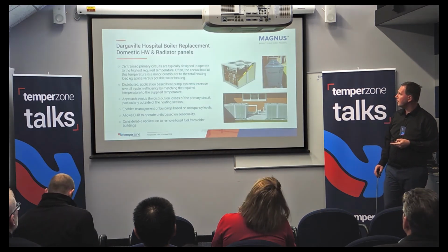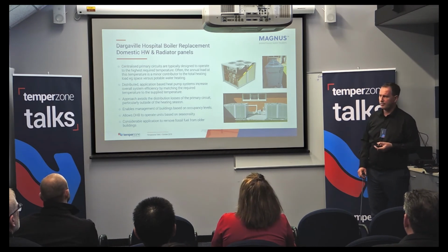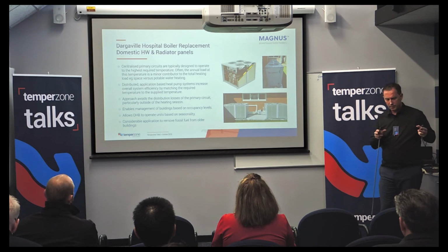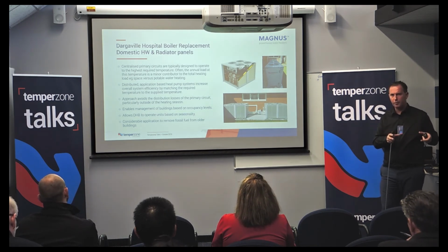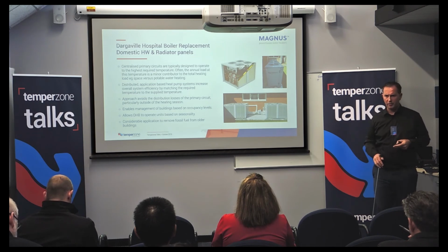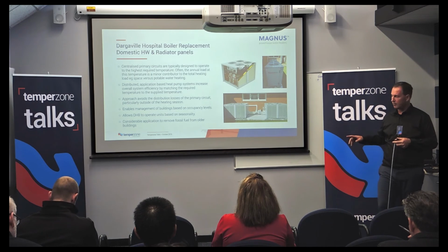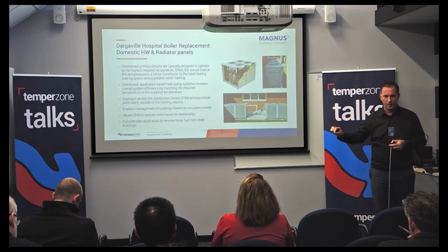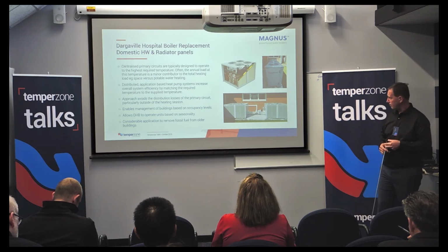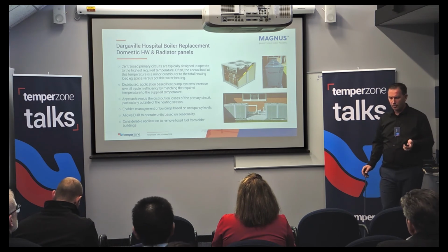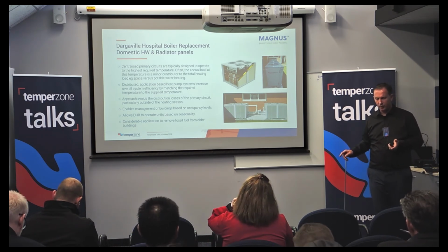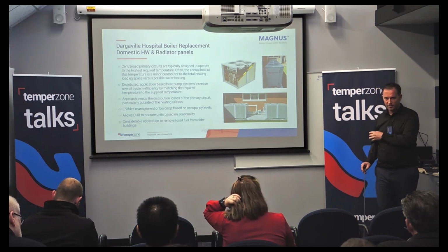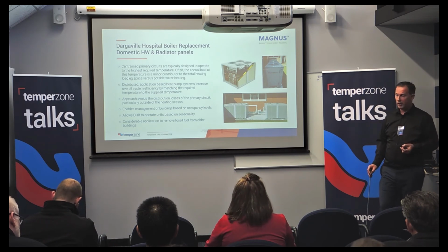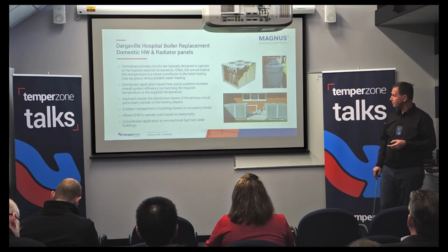And the energy savings from doing this are really huge, because you're applying the appropriate temperature hot water to the appropriate application, rather than running the entire system to the hottest application of the site. And it really works on this inverter-based part load performance of the systems. It means that for the part of the year when you're not doing space heating, you're not running this huge network that has effectively a very small load on it.